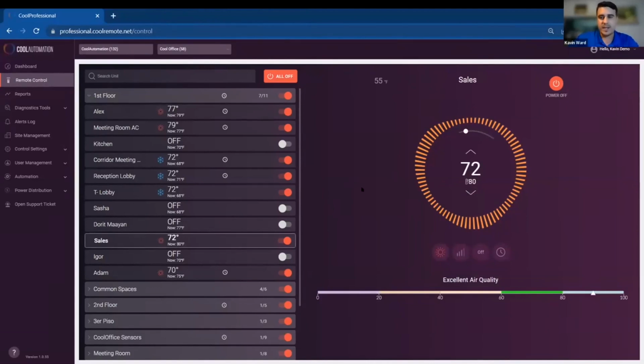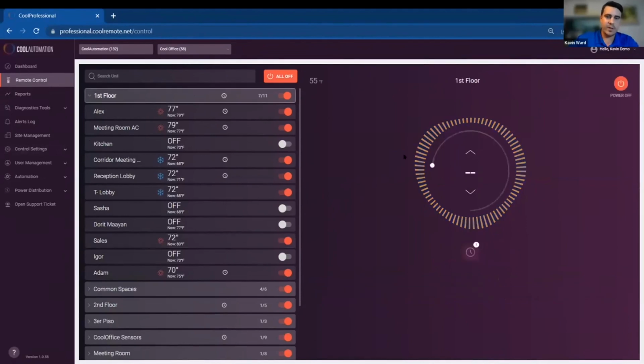Somewhere between 68 and 72 is an ideal heating set point in the wintertime. We have complete group control as well, so everything on the first floor has been assigned to a first floor group, where we have global set point control of all the units associated with that floor, as well as the ability to apply a schedule to each of these indoor units.